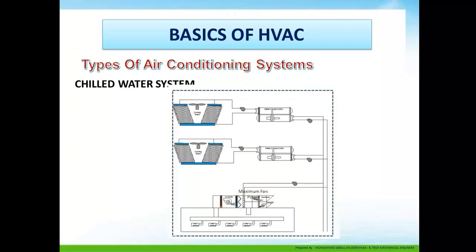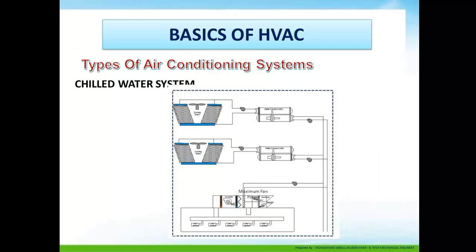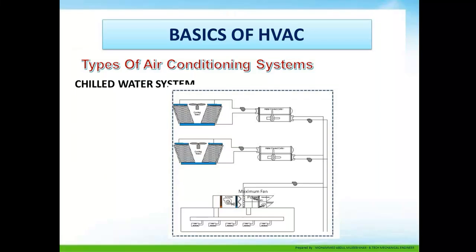A typical example of a chilled water system: you can see the cooling tower, chiller, fan coil, air handling unit, and fan coil unit. In the chiller, the refrigerant acts as the primary system, while the water flowing through the evaporator of the chiller to the AHU and the fan coil unit acts as the secondary system, where chilled water is supplied.